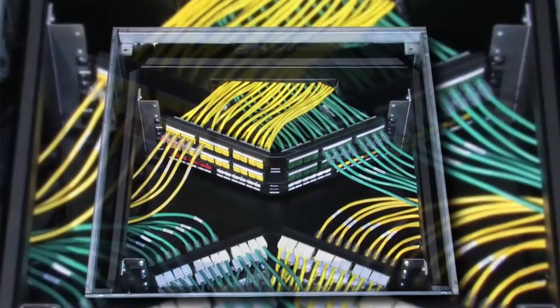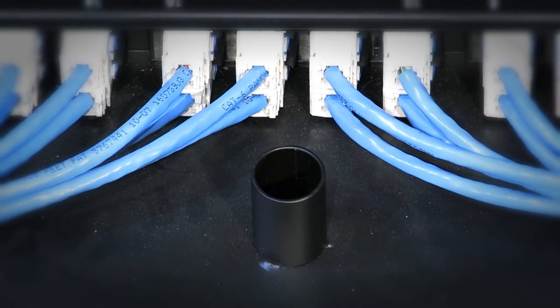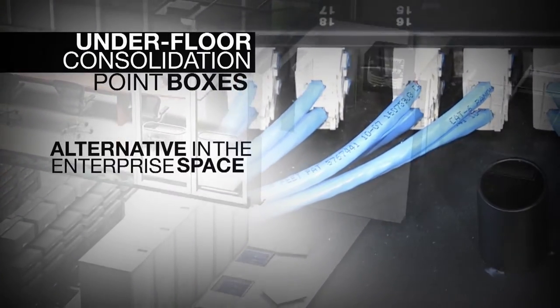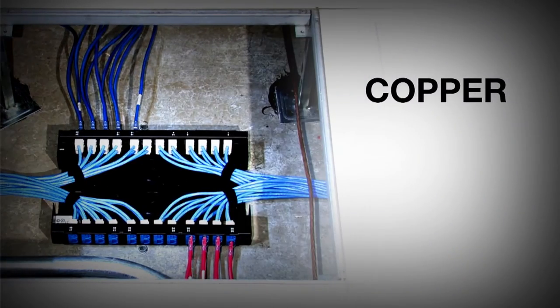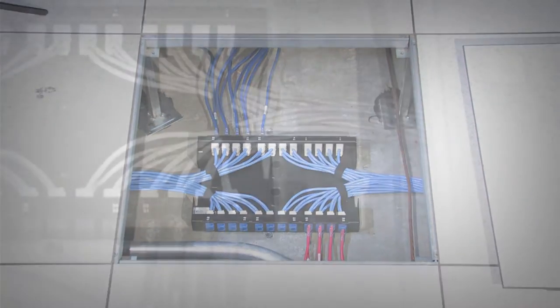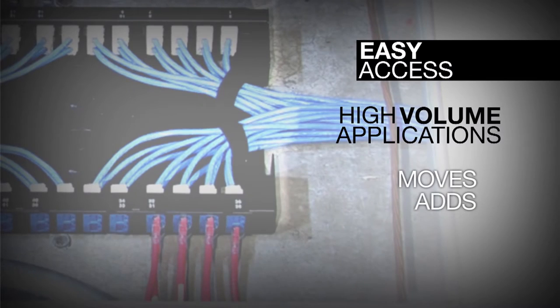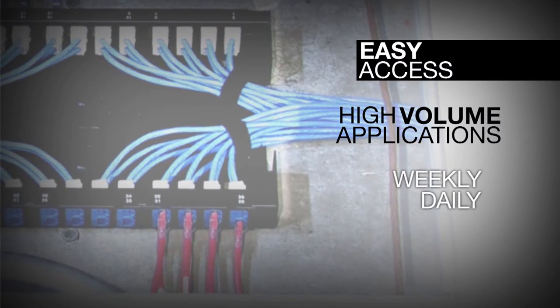With the increased use of raised floor designs, underfloor consolidation point boxes can be used as an alternative in the enterprise space. These are available in both 24 and 48 port versions for both copper and fiber systems. The enclosures can also be wall-mounted for easy access to high volume applications in which multiple moves, adds, and changes are made on a weekly or even daily basis.